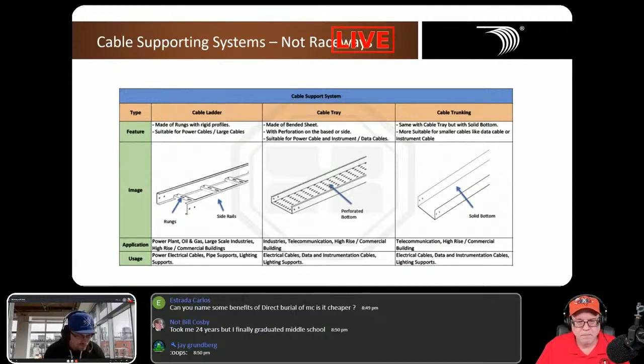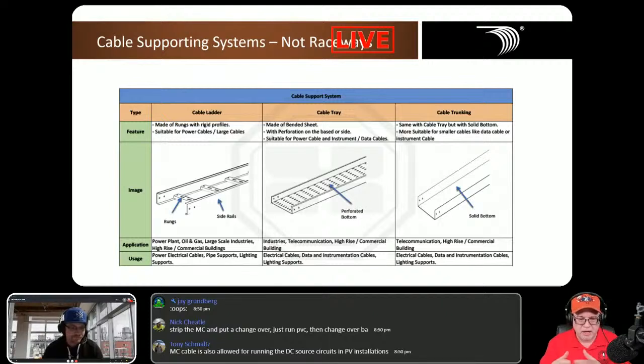Can you name some benefits of direct burial of MC? Is it cheaper? I'm not going to say it's cheaper, because there's a lot more involved. With MC, you've got the inner conductors, which incidentally are exactly the same as a tray cable's inners. They're all the same. But putting conductors directly in the burial ground, like a direct burial USE-2, is probably going to be cheaper than a PVC jacketed MC. You can do tray cable direct buried, and that might ultimately be cheaper than an MC. But a lot of people love MC because it can transition between the ground and into a building, whereas tray cable could not, without a splice point.